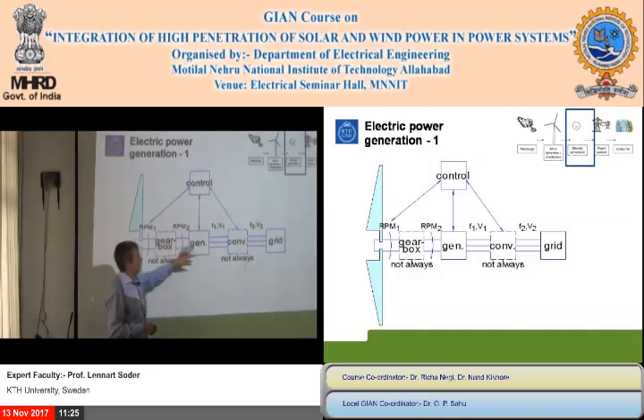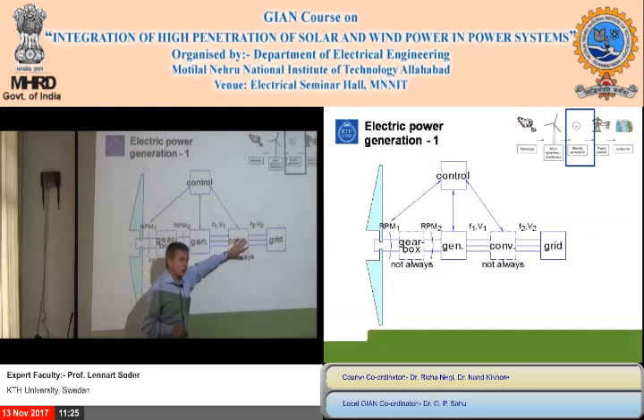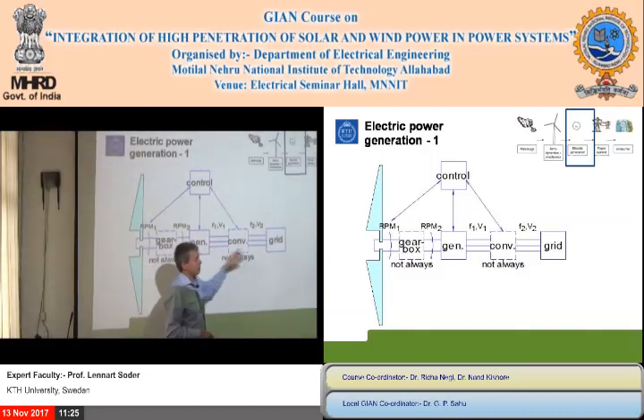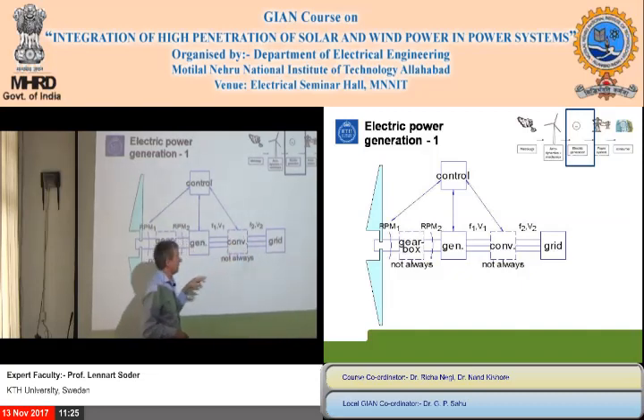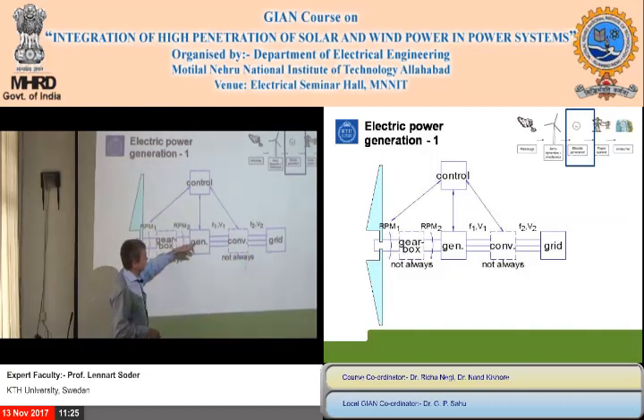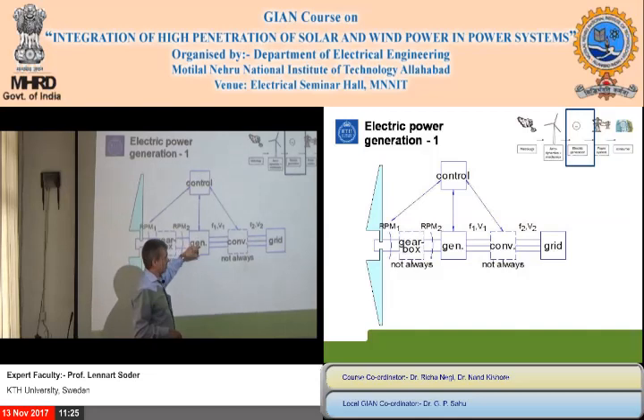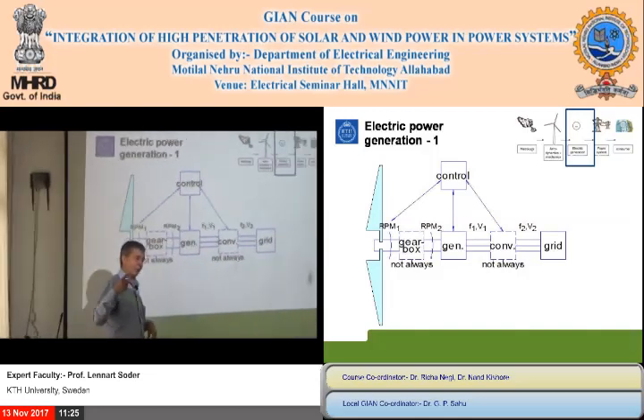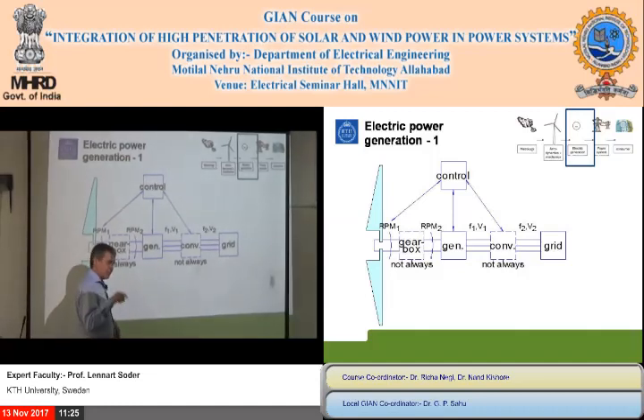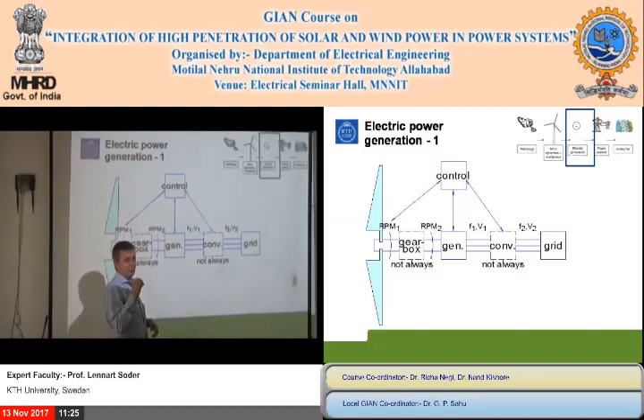That's okay if you have a converter here. If you don't have a converter, if there's a direct connection between the generator and the grid, then the speed of the generator is in reality set by the grid. That is extremely important to understand about an electric machine: when connected to a grid, there's an extremely strong connection between the speed of the shaft, the rotor speed, and the electric frequency.